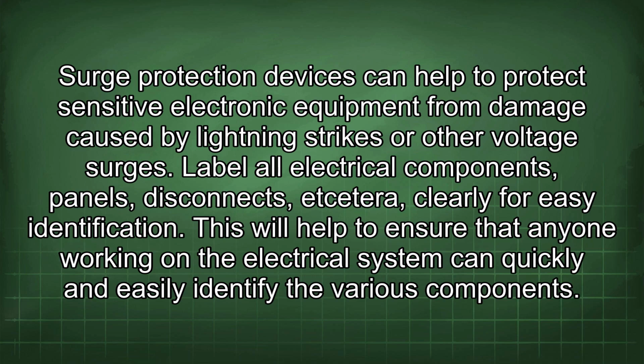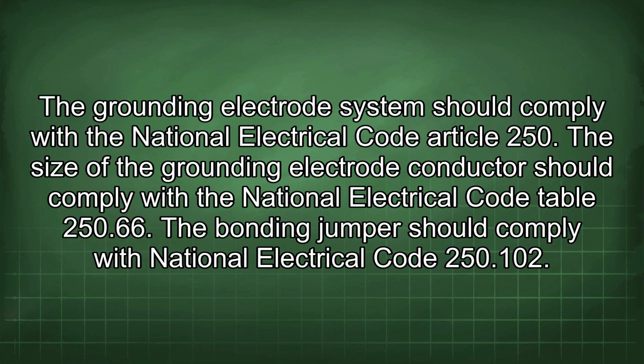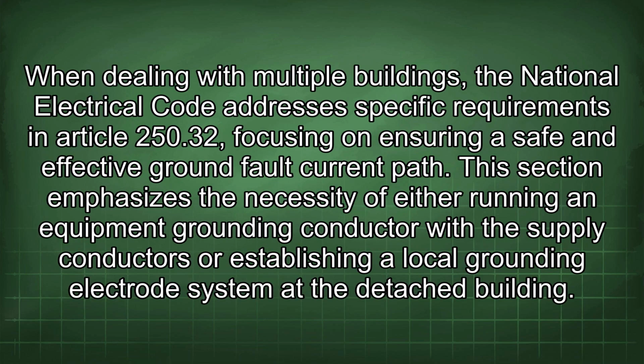Label all electrical components, panels, disconnects, etc. clearly for easy identification. This will help to ensure that anyone working on the electrical system can quickly and easily identify the various components. The grounding electrode system should comply with the National Electrical Code Article 250. The size of the grounding electrode conductor should comply with the National Electrical Code Table 250.66. The bonding jumper should comply with National Electrical Code 250.102. When dealing with multiple buildings, the National Electrical Code addresses specific requirements in Article 250.32, focusing on ensuring a safe and effective ground fault current path.